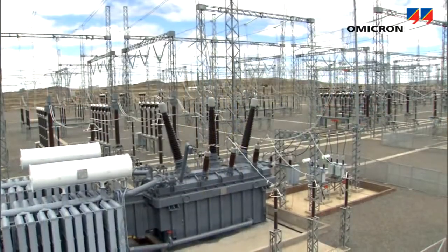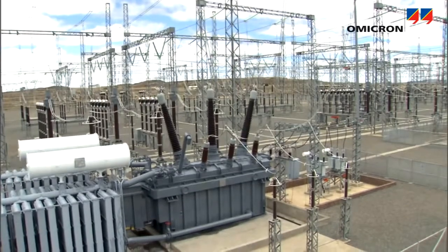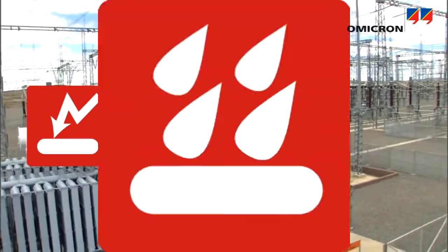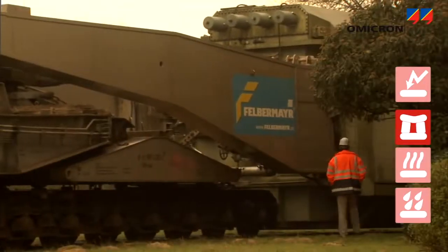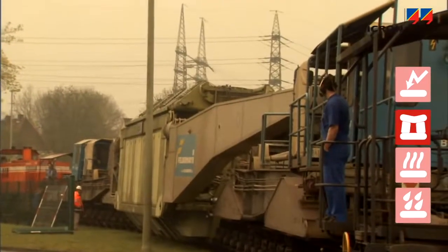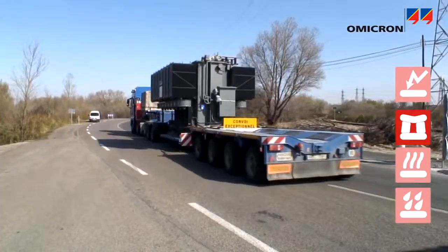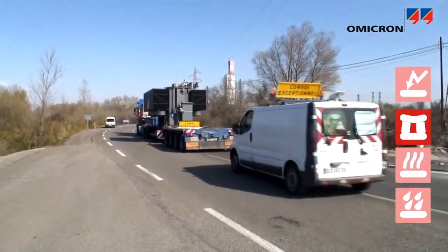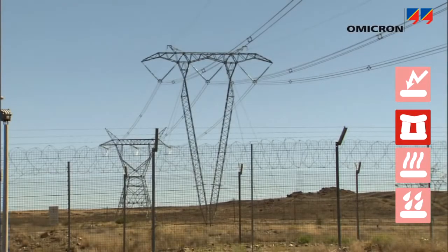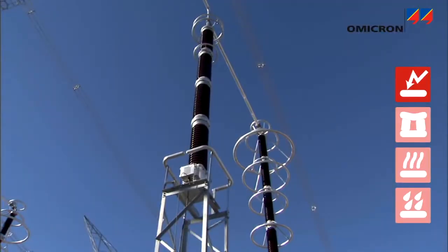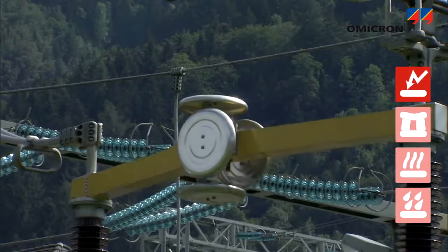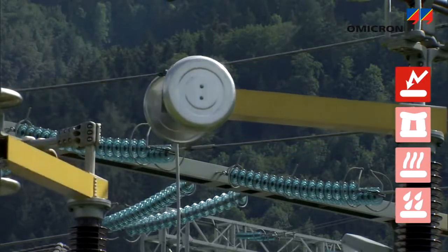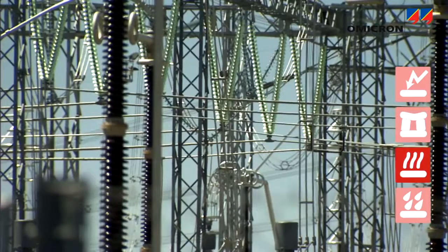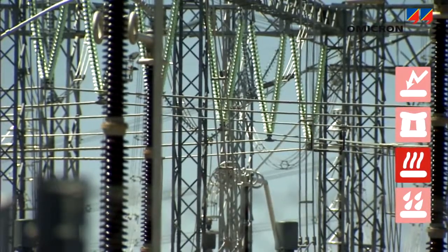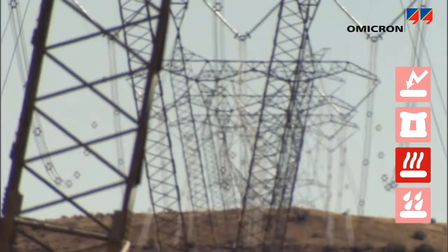During regular operation, and in particular during an electrical fault, power transformers are subject to electrical, mechanical, thermal, and environmental stresses. Power transformers are exposed to mechanical stress during transport from factory to site, during relocation from one substation to another, during earthquakes, or during external short-circuit faults. Transformers have to withstand the stress of operating voltages, as well as pulse voltages like lightning or switching pulses. The inner losses, dominantly caused by load current, must be dissipated. High temperature causes deterioration of the transformer's insulation materials.